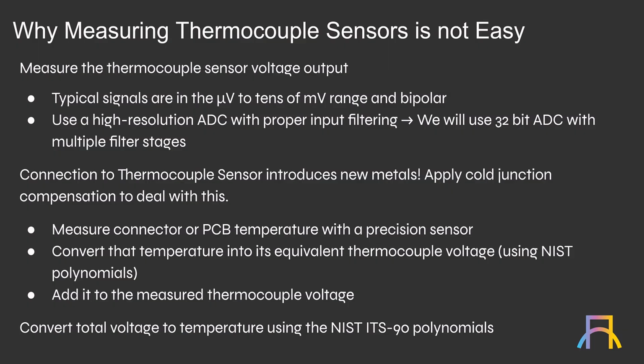The other part of a thermocouple that makes it tricky to measure is that the thermocouple is all based on two dissimilar metals that you know about. If we connect the sensor to a board, we typically have to add another metal to the mix, whether that's a screw terminal connection, a crimp connection, or, in my demo, I soldered the probe directly to the precision logger board. All that introduces new metals, which adds more Seebeck effects.